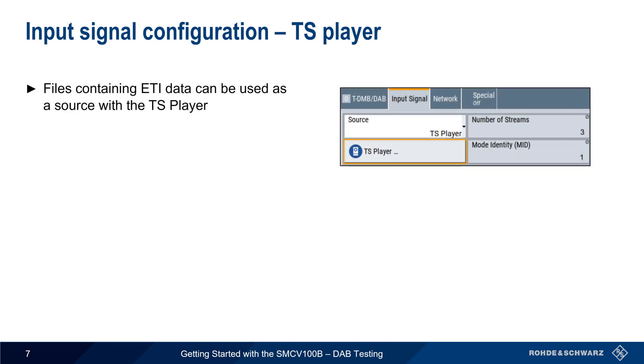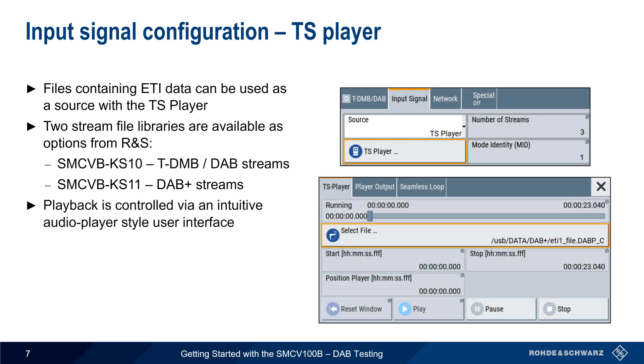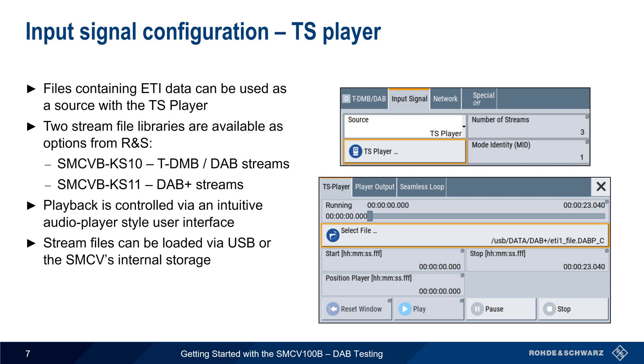ETI data in the form of a file can also be used as a source by selecting TS player as a source option. Two stream file libraries are available from Rohde & Schwarz: the KS10 library contains standard DAB streams, and the KS11 library contains DAB Plus streams. These libraries can be directly downloaded from the Rohde & Schwarz website, but playback requires the appropriate license file. The playback of stream files is controlled via an intuitive audio player type interface, and files can be played from an attached USB drive or copied to the SMCV's internal storage.